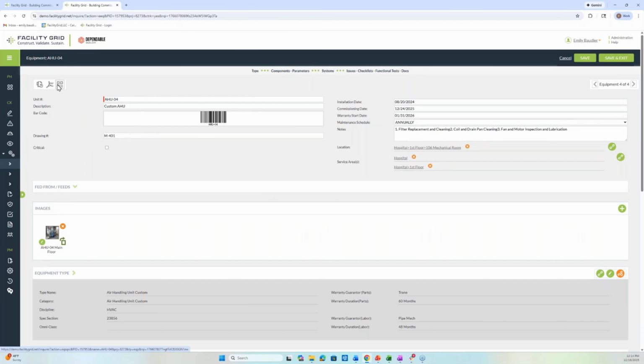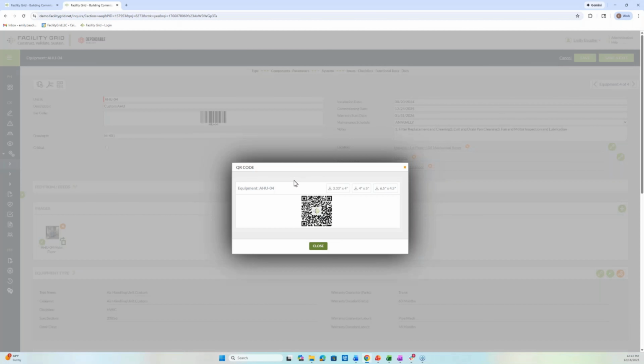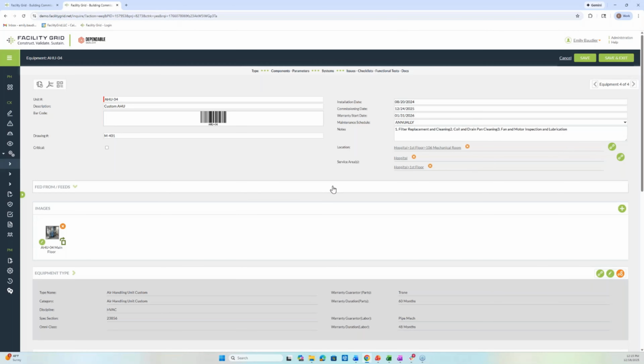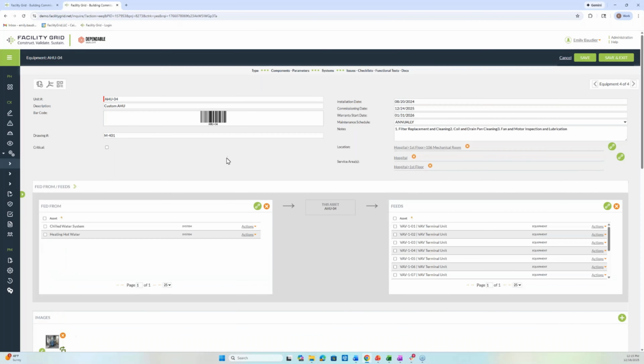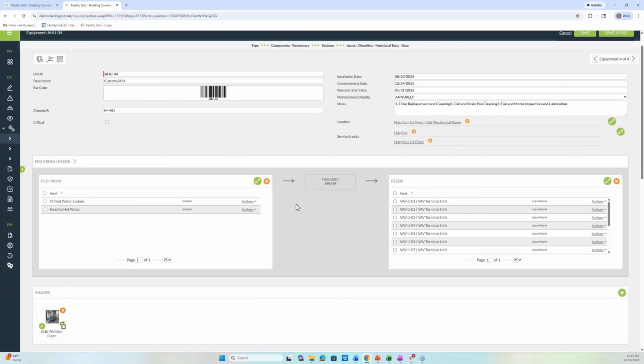And I'm even able to export a QR code that I can place at that piece of equipment, so if this QR code is scanned on your mobile device, it'll bring you to your asset record. I notice as well that this asset is on the first floor mechanical room, and it's servicing our hospital first floor area. Then if I click this dropdown, I can see that the chilled water system as well as the heating hot water system are feeding air handling unit 4, and air handling unit 4 serves VAVs 1 through 7.